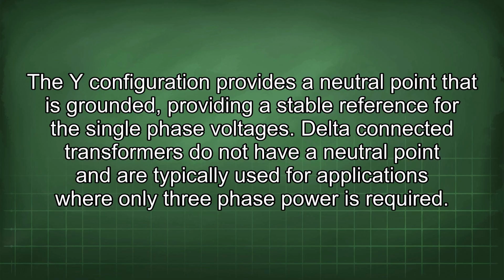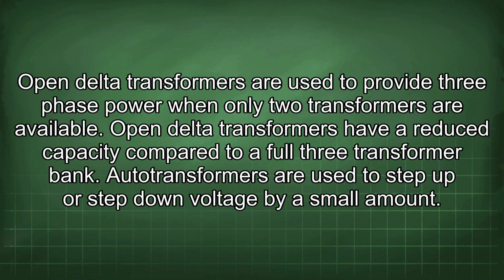Delta-connected transformers do not have a neutral point and are typically used for applications where only three-phase power is required. Open delta transformers are used to provide three-phase power when only two transformers are available. Open delta transformers have a reduced capacity compared to a full three-transformer bank.